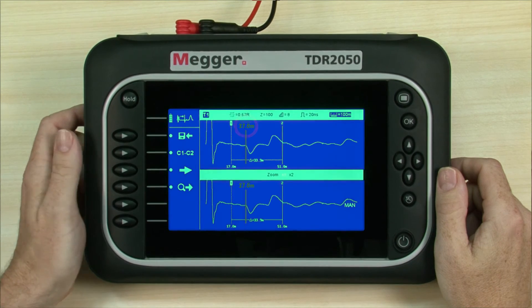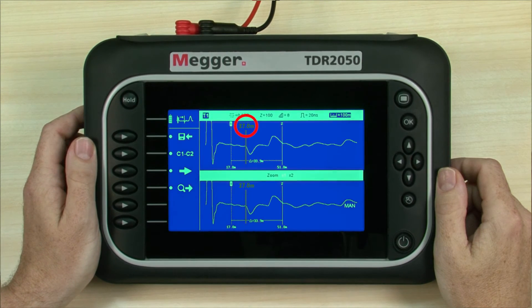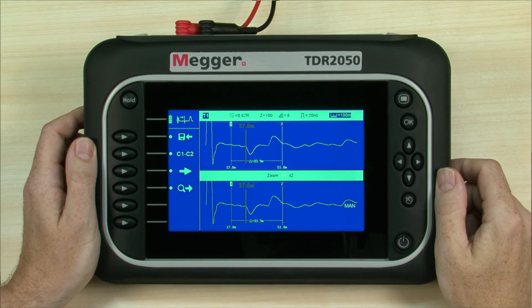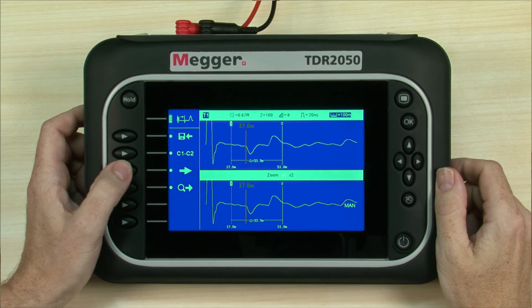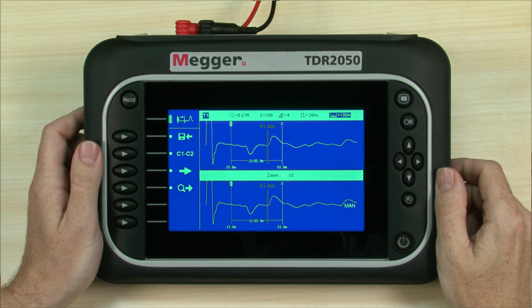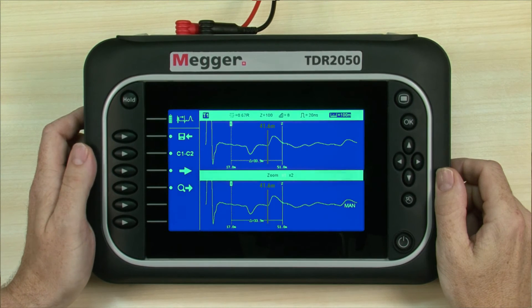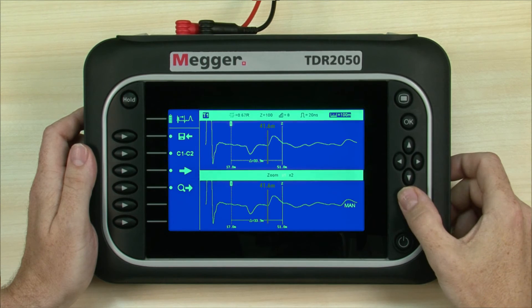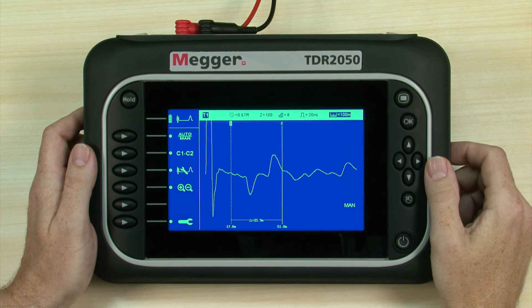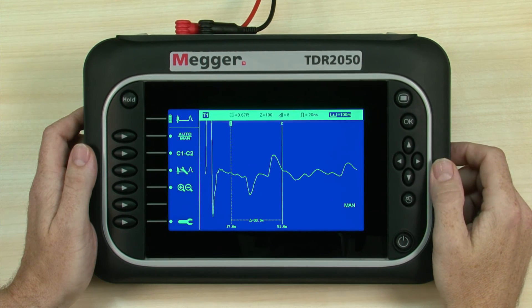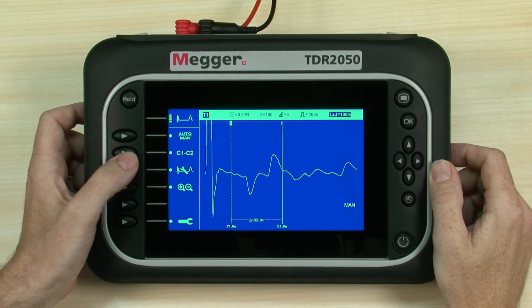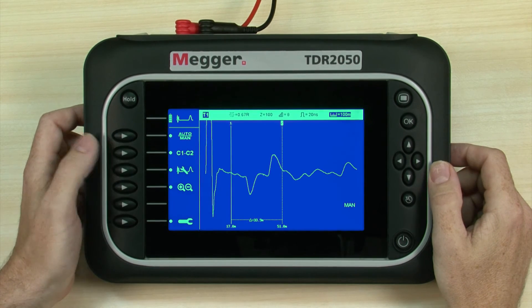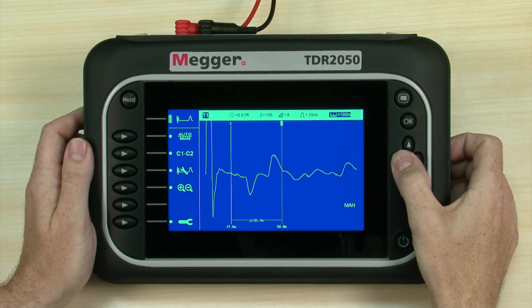An event has been detected and a marker placed at this point. The distance is shown at the top of the marker. Pressing the Find Next soft key automatically positions the cursor at the next event. Now let's return to the main screen, where we can easily measure the distance between two events. TDR 2050 has two cursors, which can be positioned at different events on the trace giving the distance.